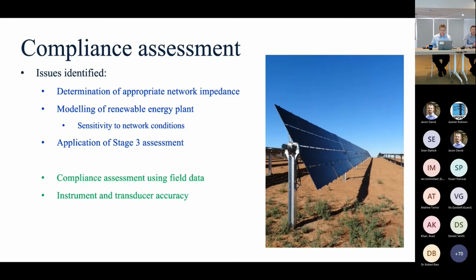In terms of pre-connection, number one is determination of appropriate network impedance, and there have been some conversations around that already. Many NSPs are now requiring the use of polygons, and whether or not we think that's the right way is a little uncertain. How we model the renewable energy plant remains uncertain, and the sensitivity of that plant to prevailing network conditions, whether that be impedance or background harmonic distortion in the voltage, is another issue that has come up. There's uncertainty there. How we go about application of stage 3 assessment in 61000-3-6: by what mechanisms can we potentially allow plant to connect and see what might happen? I think that's less of a technical issue and maybe more of a regulatory issue or a connection framework type issue.